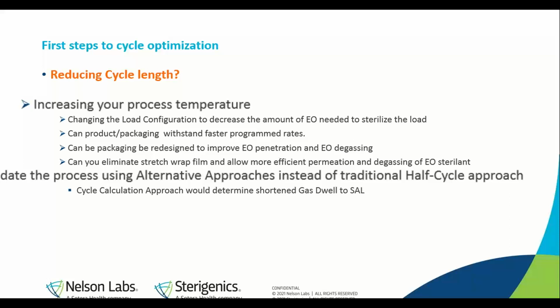One example in this is, don't just look at the packaging of the product, but the packaging of the load. And what I mean by that is looking at how we use stretch wrap, or the traditional film that gets used to wrap the pallets. Although used as a way to restrain the load on the pallet, it can also be a barrier that you have to deal with in terms of getting ethylene oxide through that film before it even starts penetrating through your corrugated shipper boxes, and eventually work through the load into the hardest to locate BIs in your product. You can eliminate stretch wrap film and allow more efficient penetration and degassing of the EO sterilant.